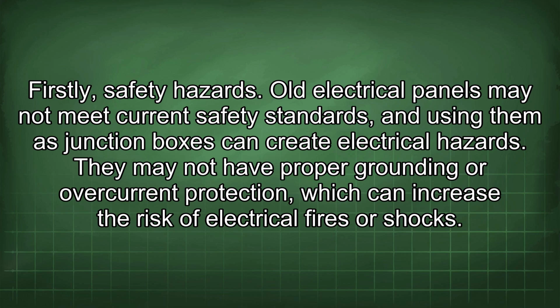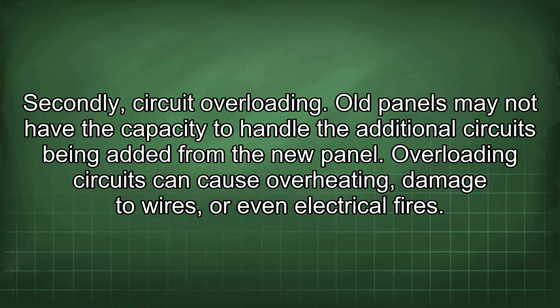Firstly, safety hazards. Old electrical panels may not meet current safety standards, and using them as junction boxes can create electrical hazards. They may not have proper grounding or overcurrent protection, which can increase the risk of electrical fires or shocks. Secondly, circuit overloading. Old panels may not have the capacity to handle the additional circuits being added from the new panel. Overloading circuits can cause overheating, damage to wires, or even electrical fires.